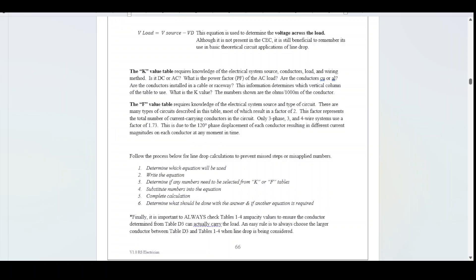The F-value table requires knowledge of the electrical system source and the type of circuit. There are many types of circuits described in this table, most of which result in a factor of 2. This factor represents the total number of current-carrying conductors in the circuit. Only three-phase three- and four-wire systems use a factor of 1.73, due to the 120-degree phase displacement of each conductor resulting in different current magnitudes at any moment in time.